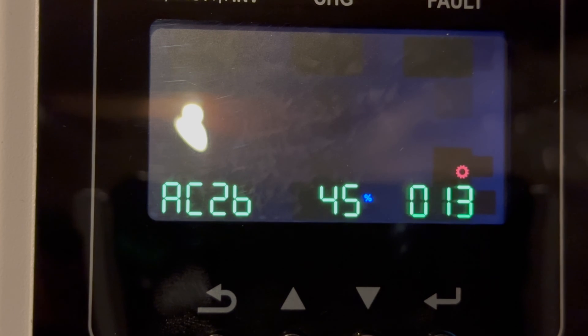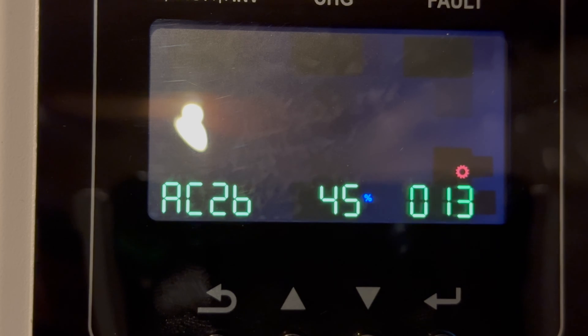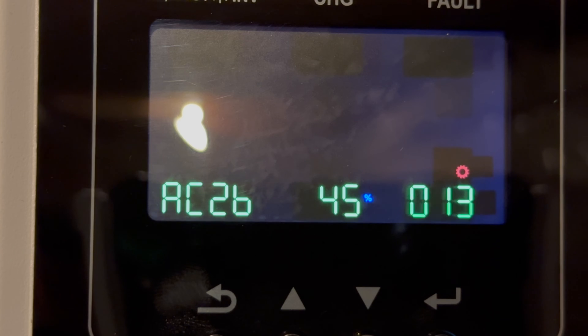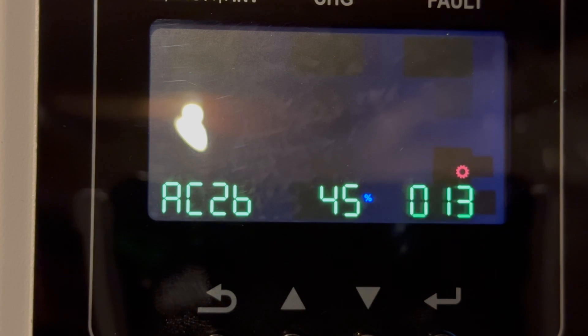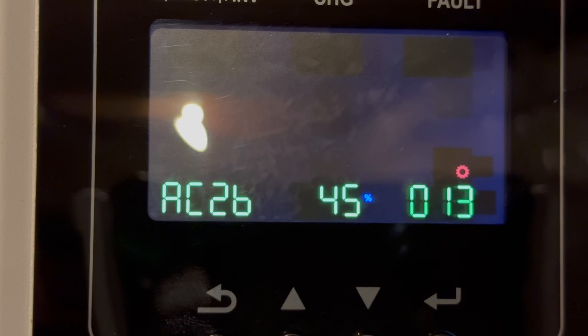Setting 13 determines the charge of the battery that will take over load from the grid when the battery is being charged. So if the battery is being charged up to 45%, once it hits 45%, it will start carrying the loads. That may mean the battery goes back down, but if there's solar, generally the solar charges up to 45%, starts carrying the loads of the house, and then continues charging it.